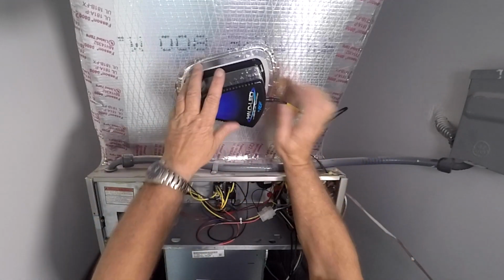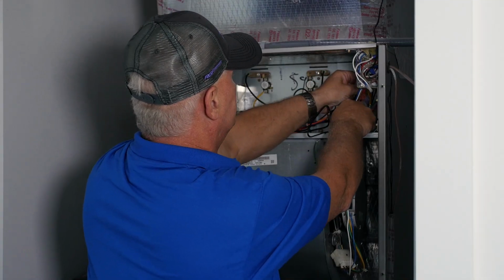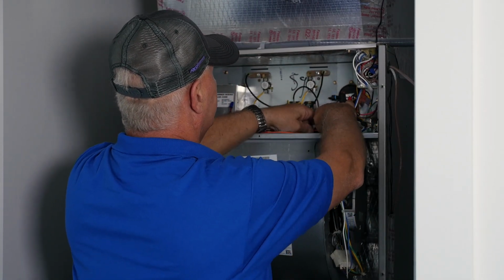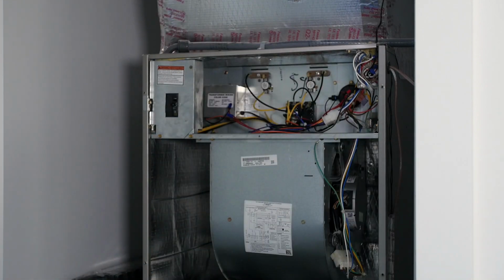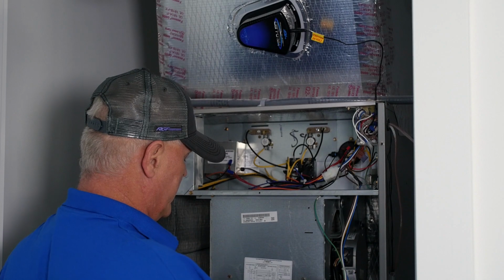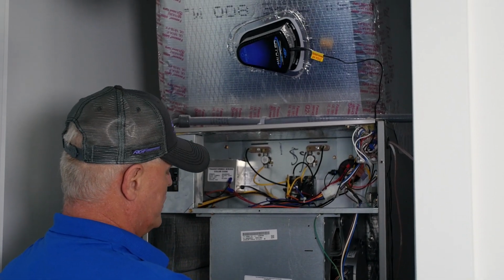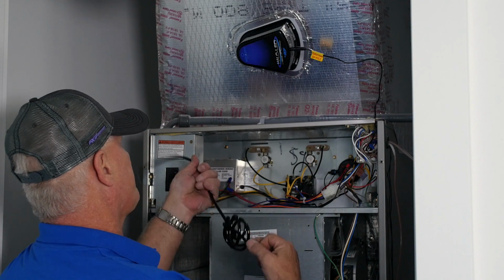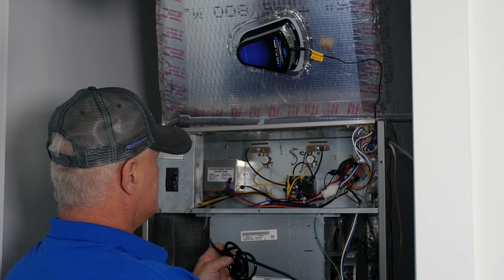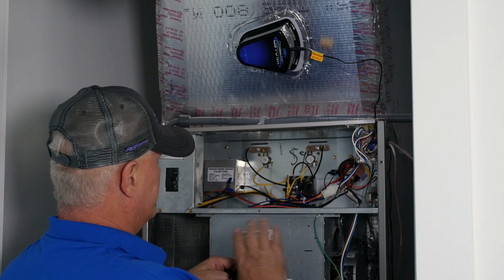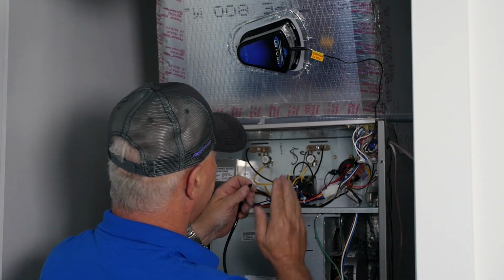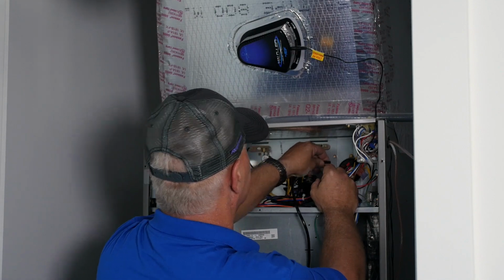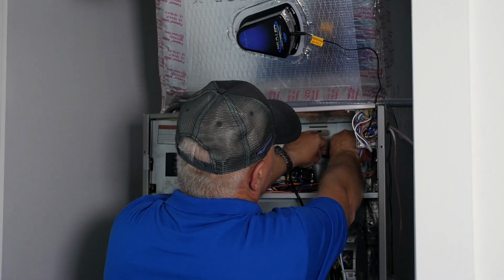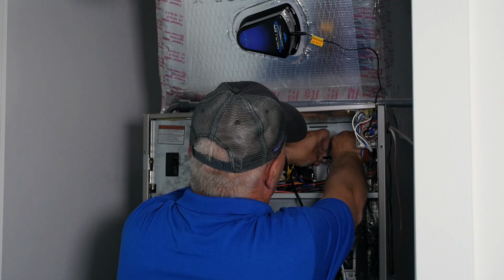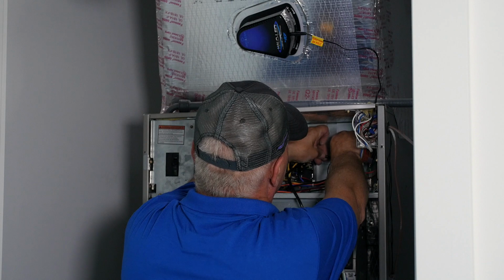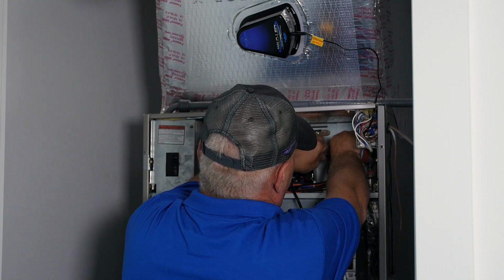You can plug the REMI in right now. It will not come on because we do not have power to the unit. We are now going to run our signal to turn the switch on and off using the 1/4 inch OD tube which comes in the kit. Because we have the air switch mounted inside the unit where it's going to get the low pressure, we are going to put our sensor tube onto the positive or high pressure side of the switch, as such.